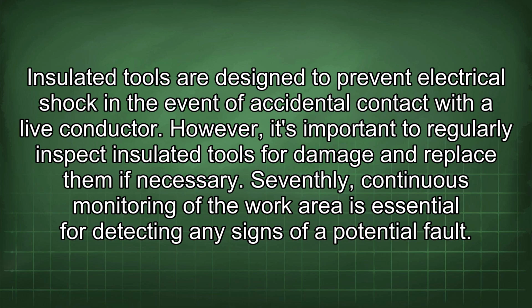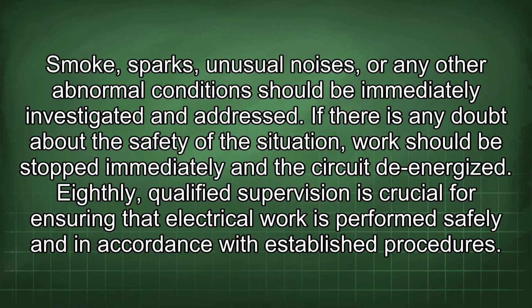Seventhly, continuous monitoring of the work area is essential for detecting any signs of a potential fault. Smoke, sparks, unusual noises, or any other abnormal conditions should be immediately investigated and addressed. If there is any doubt about the safety of the situation, work should be stopped immediately and the circuit de-energized.